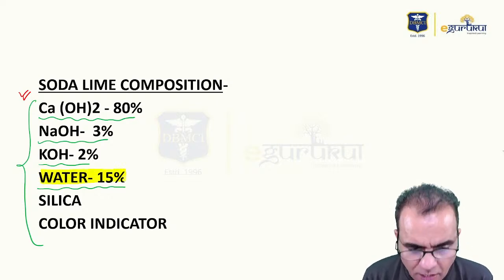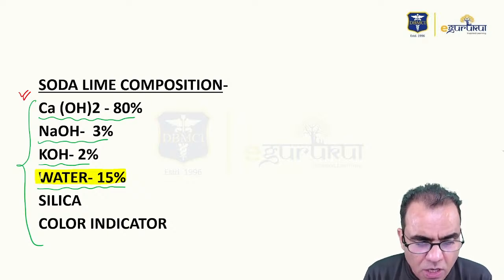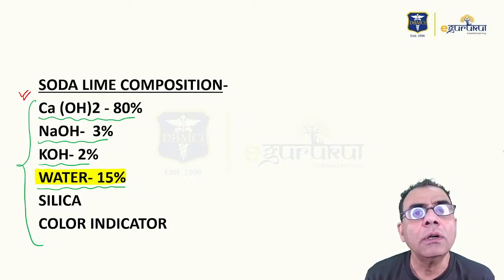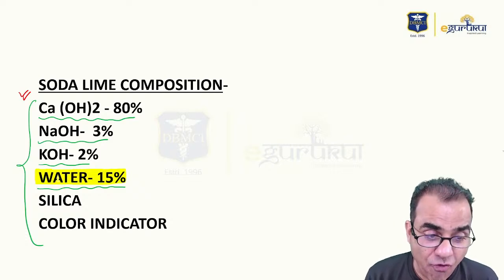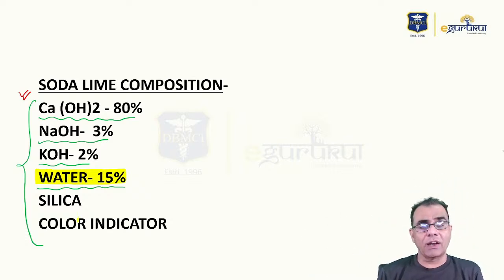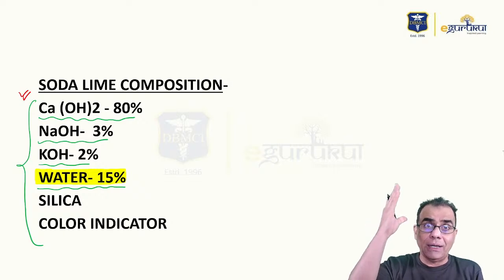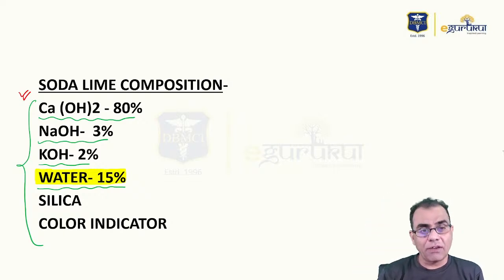In older times, maybe in a few old editions of the books, you will find that it is given calcium hydroxide 95%, no water. So that is a major and a very important change. The significance of that we are just going to see: the currently used soda lime has 80% calcium hydroxide. They have reduced calcium hydroxide from 95% to 80% and replaced it with 15% of water. Why? I'll tell you the significance later.